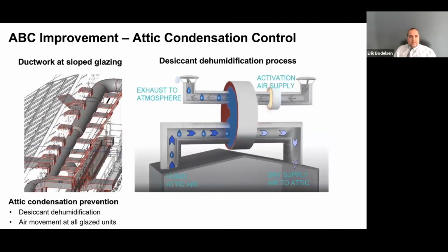Desiccant dehumidification systems designed to dry out the air supply to the attic, seen in the graphic to the right, vastly decreasing the dew point temperature, was also a significant improvement in the attic space. And we also ducted dry air to all glazed surfaces in the attic, as can be seen on the graphic on the left. This ensures dry air moving across the glass, preventing condensation from forming. All of these measures resulted in a substantial energy improvement from the previous approach.